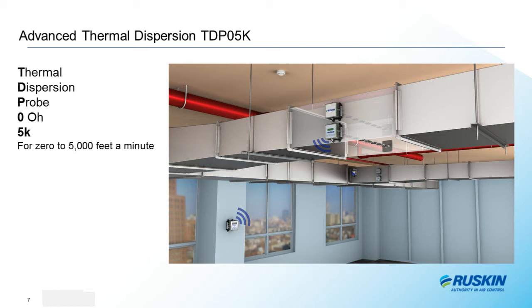Shown here is our wireless remote display on the wall with an 8-sensor primary probe installed in the duct and an 8-sensor ancillary probe installed in that same duct. The large, bright remote display is an interior decorator or design engineer's dream come true. The remote display looks great on any wall in your control room and can be installed wirelessly up to 200 feet from the primary probe or wired up to 500 feet from the air measurement station, no longer limited to a 50-foot distance.